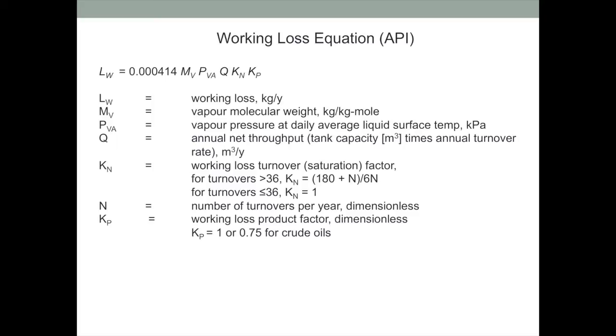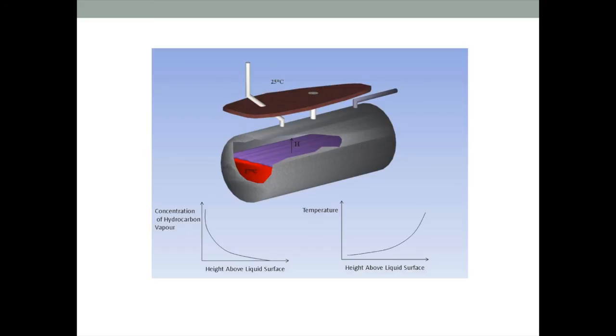They also apply a correction factor based on the type of product being handled — one for refined products and 0.75 for crude oils — without really explaining why it would be less for crude oils. Inherent in the API algorithms is an assumption that you have some degree of stratification in the tank. When you pull air in, you'd have fresh air at the top towards the vent and a richer air-vapor mixture towards the liquid surface. As the tank fills and you get towards the top of the fill cycle, you would start to displace the emissions at some percentage of the saturation level for that total mixture.